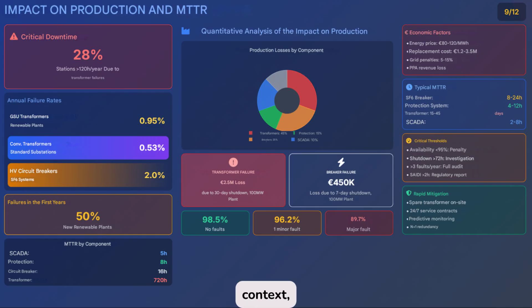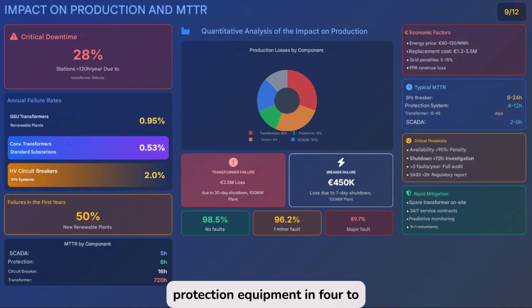In this context, MTTR, or mean time to repair, becomes a critical variable that often doesn't receive the attention it deserves. While systems like SCADA can be back online in 2 to 8 hours and protection equipment in 4 to 12, circuit breakers require between 8 and 24 hours. But transformers pose the greatest challenge. Their repair can take between 15 and 45 days, in some cases reaching up to 720 hours.